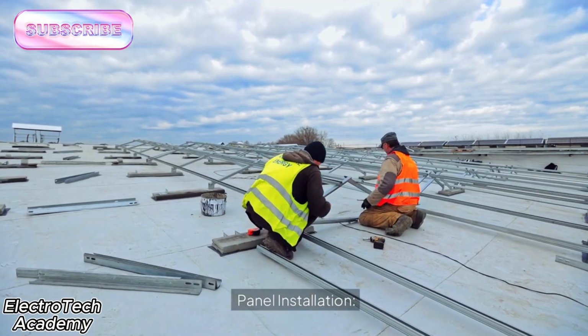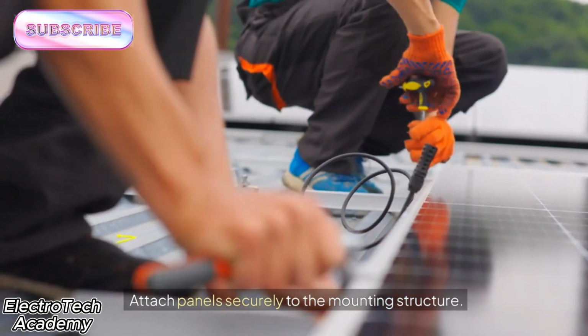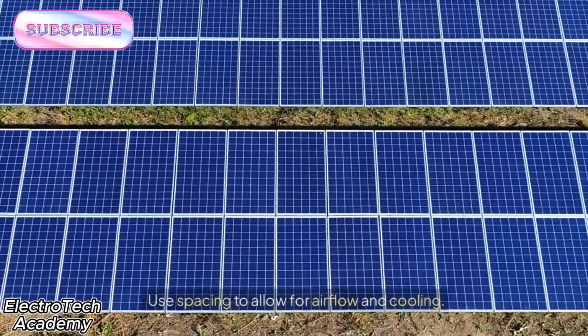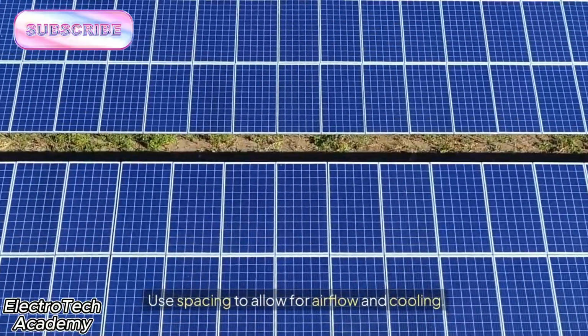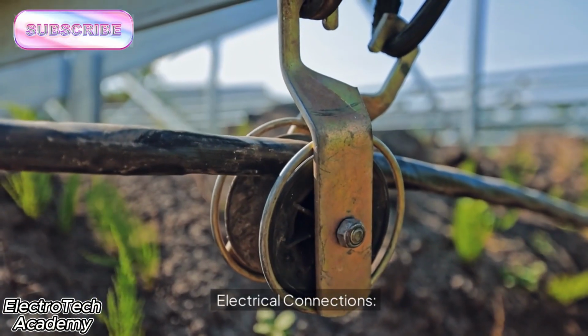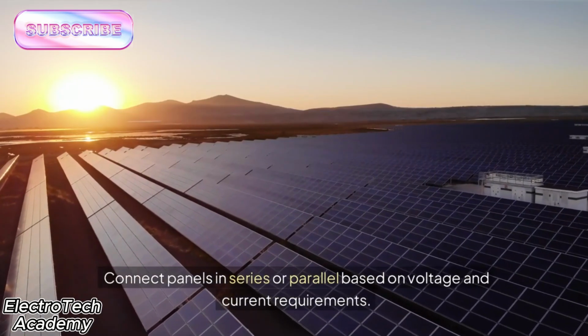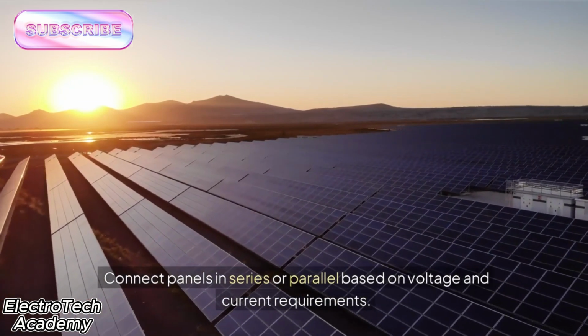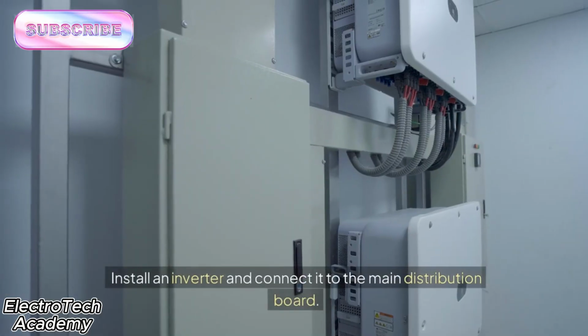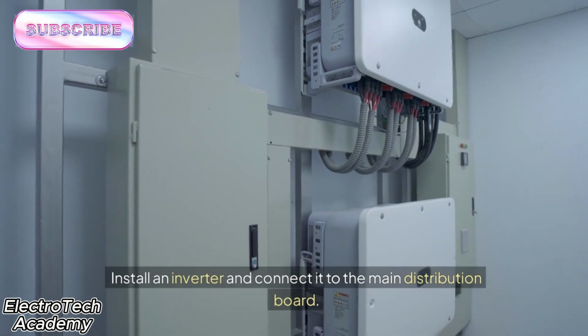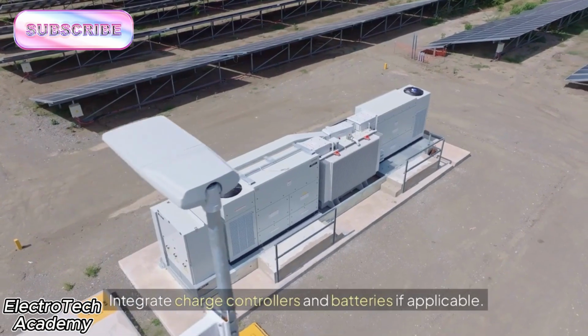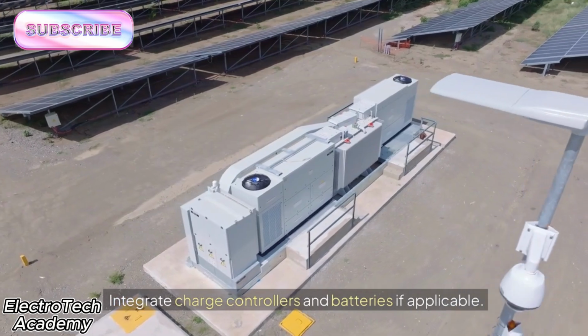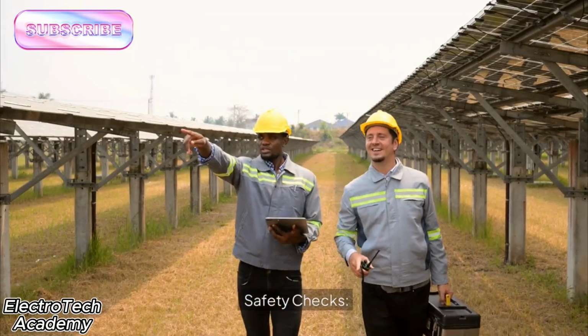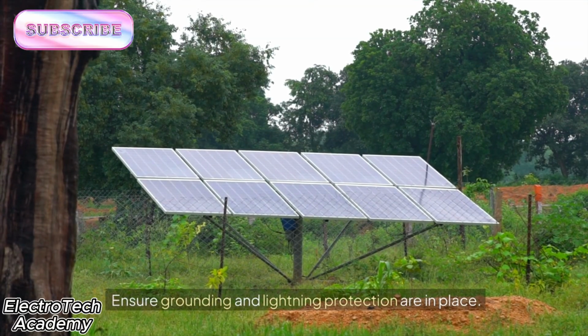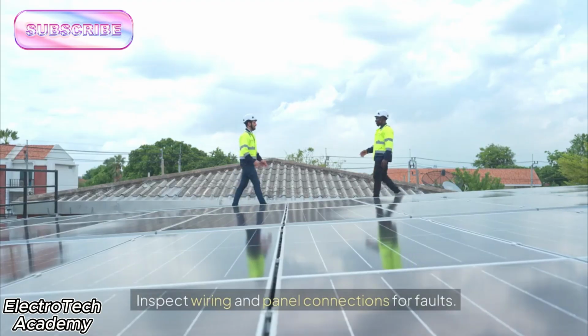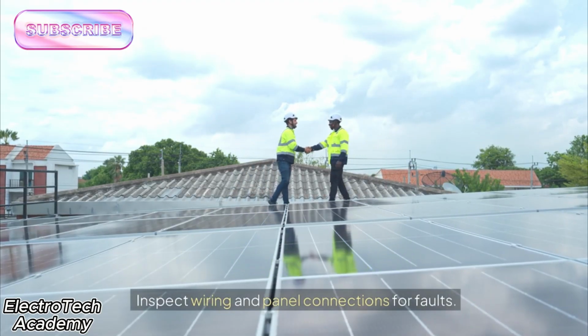Panel installation. 1. Attach panels securely to the mounting structure. 2. Use spacing to allow for airflow and cooling. Electrical connections. 1. Connect panels in series or parallel based on voltage and current requirements. 2. Install an inverter and connect it to the main distribution board. 3. Integrate charge controllers and batteries if applicable. Safety checks. 1. Ensure grounding and lightning protection are in place. 2. Inspect wiring and panel connections for faults.